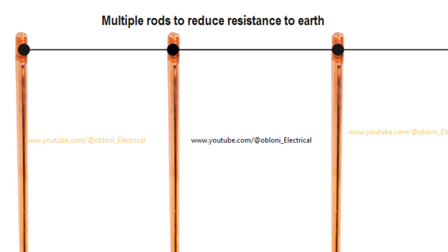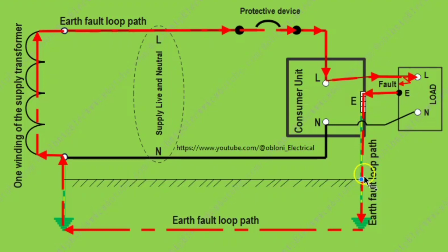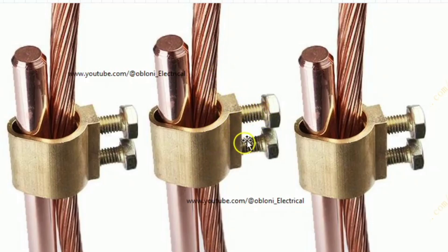In simple terms, proper earthing simply means providing a very low resistance path for fault currents that may occur between live conductors and earth to flow to earth. When connecting your earthing conductor to the earth electrode, you must use earth clamps for the connection, because that provides a good connection between the earthing conductor and the earth electrode. The earth fault loop path must have a very low resistance, and that includes the resistance at the termination of the earth electrode.